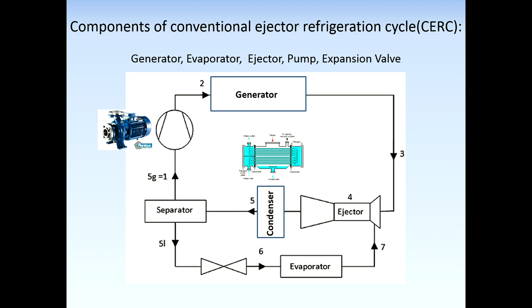Regarding the generator, as mentioned, using dissipative energies, solar energy, or geothermal energy we can prepare the heat for the generator. In a refrigeration cycle with a solar energy generator, solar collectors are used in a closed secondary cycle to warm up the operating fluid, which then exchanges its heat via a heat exchanger with the refrigerant working through the cycle.